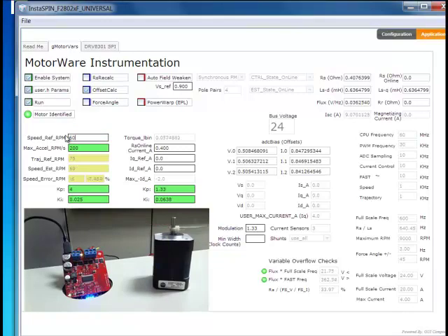So if we want to keep dropping this, we'll go to 4 hertz. It's doing pretty well, very stable. 3 hertz. And again, at this point, we're not regulating this to, let's say, 5% speed, but with no load, we still have an observer that is tracking and maintaining the speed pretty consistently. And if I had any sort of load, it gets even better because you get more current signal that you're able to put into your calculations as well.